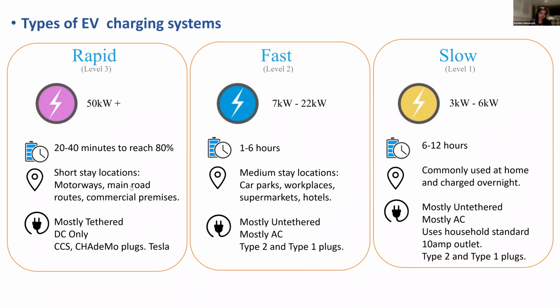Rapid charging draws 50 kilowatts plus, mostly around 75 kilowatts. If you think about having 10 rapid charging stations within a development, that's a 500 kilowatt requirement, and you'd need a small substation to provide that power. Short stay locations for this are motorways, main roads and routes, and commercial premises.